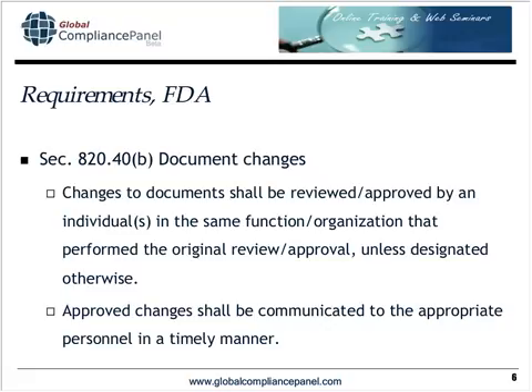I'm here to tell you this can be very, very painful if not done correctly. If you define what you consider timely and you do not meet it, you will have to do non-compliance investigations because you did not meet one of your internal requirements. This may be cited by the FDA, this may be cited to notified body, internal audit. The best way to verify timeliness of communication is by internal auditing. And you may want to explain this in your procedures. I have. If your auditors, internal, external, other, never find instances of product being assembled to obsolete procedures or inspections to obsolete drawings, for example, you can therefore conclude that your communication of changes is timely.